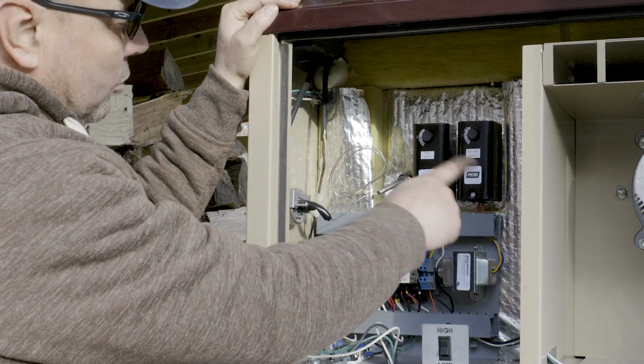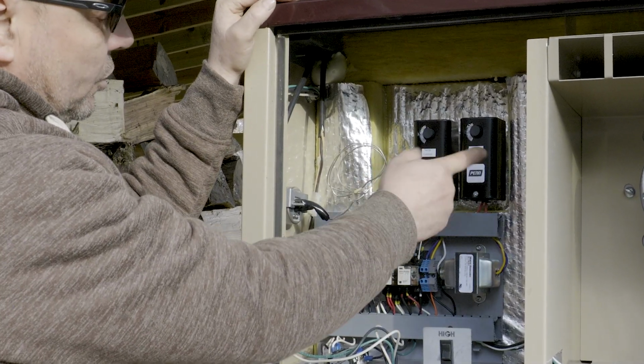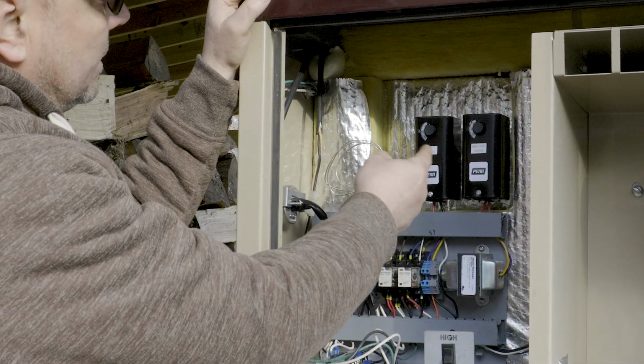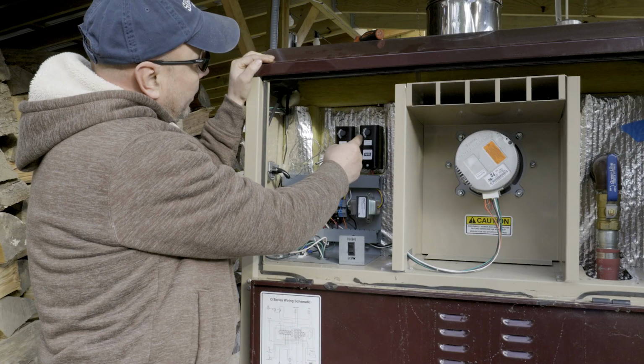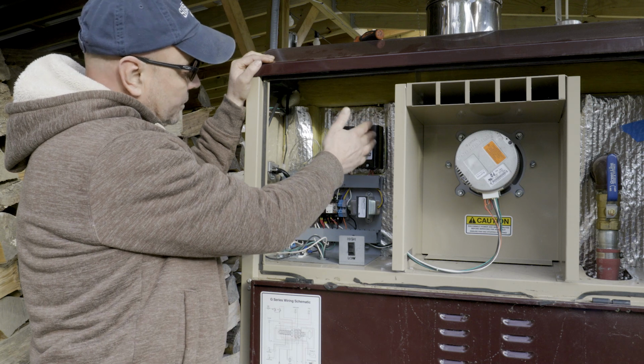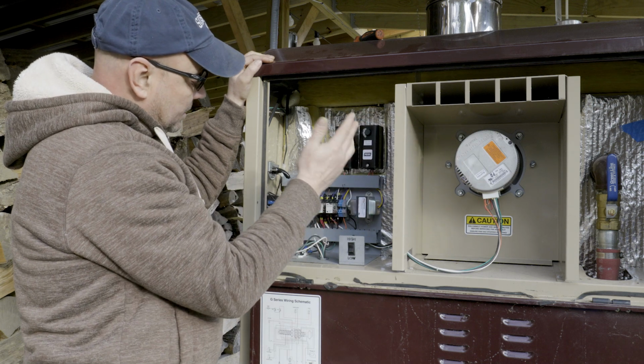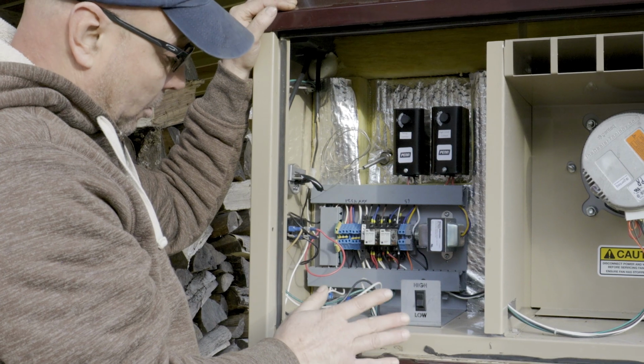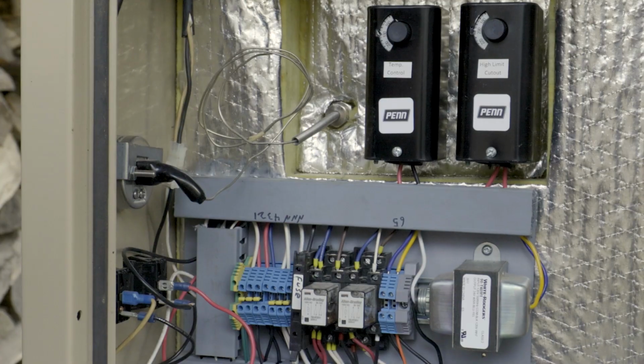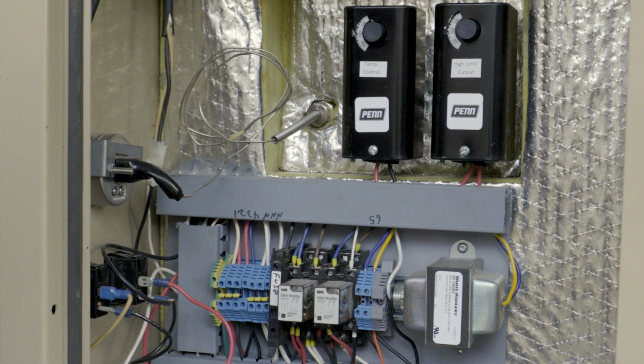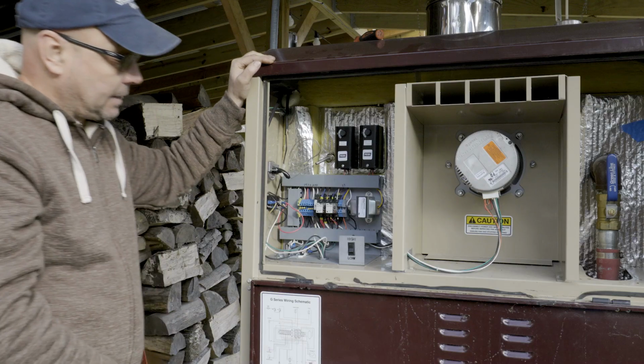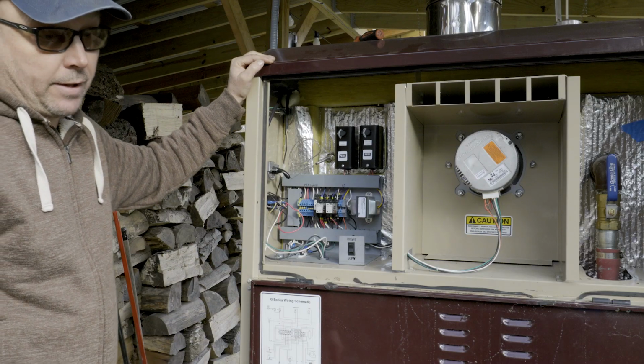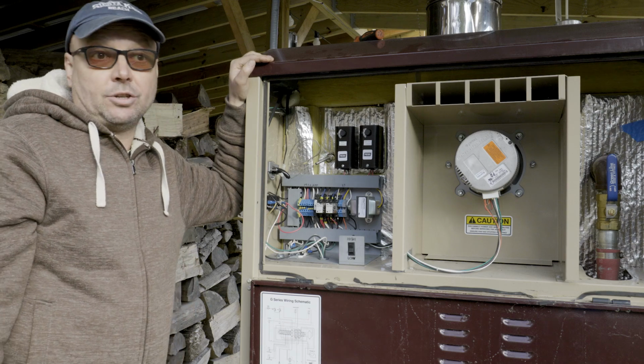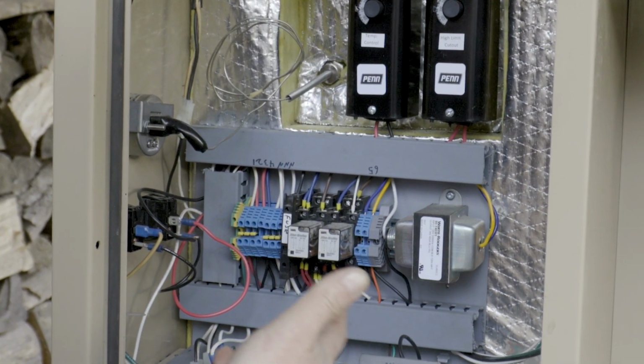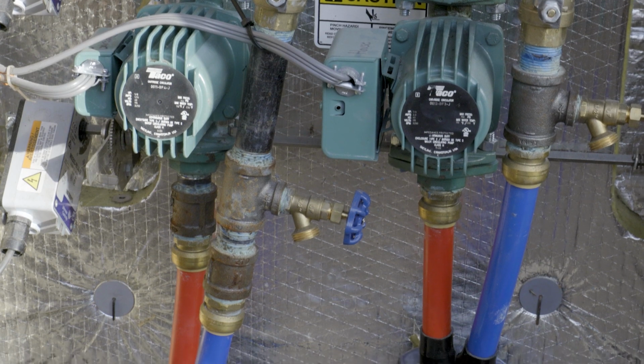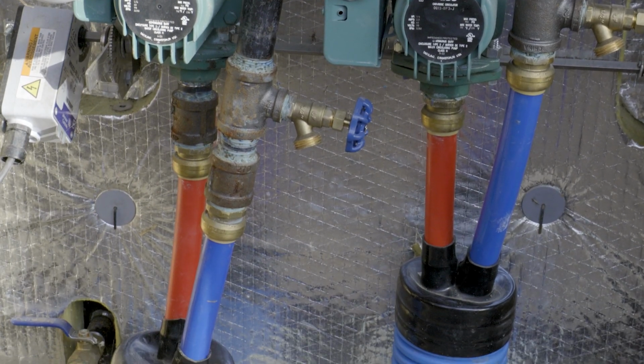This is a temperature control valve, basically an on and off switch. The design temperature is 180, where it shuts off, and at 200 it turns on the fan, depending on the call for heat. Very simple. It doesn't have any circuit boards, processors, or microswitches or anything like that. That's the thing I like about it. If you have a power or internet outage, you don't have to worry about Wi-Fi connections or Bluetooth or anything like that. You can run the whole thing with a small generator.